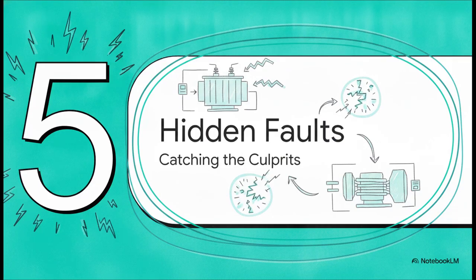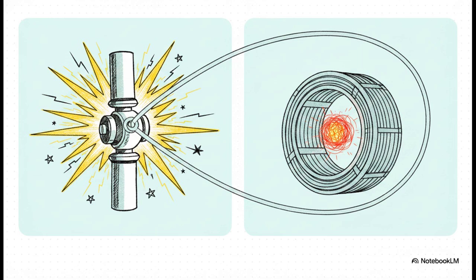Section 5. Catching the hidden faults. So the TR2PTDF function is generally on the lookout for two main culprits. On one hand, you have a bushing flashover. This is a loud, visually obvious electrical arc jumping where it shouldn't on the outside connection points. On the other hand, you have an inter-turn fault, a subtle, totally hidden short circuit deep inside the winding coils. Despite being vastly different in appearance, both create that telltale differential current imbalance, and our relay catches them both.